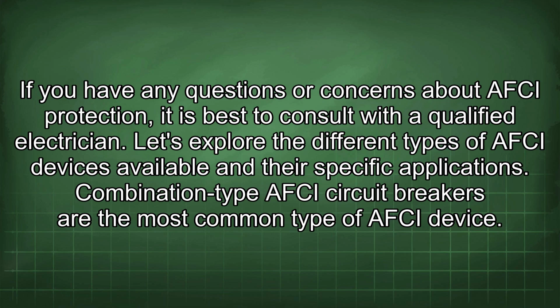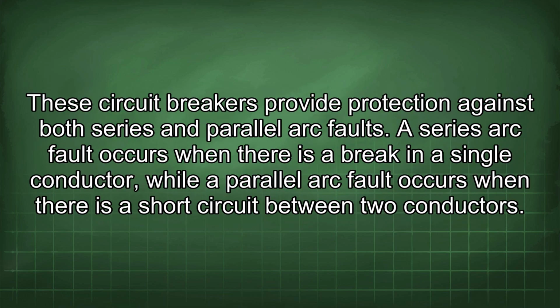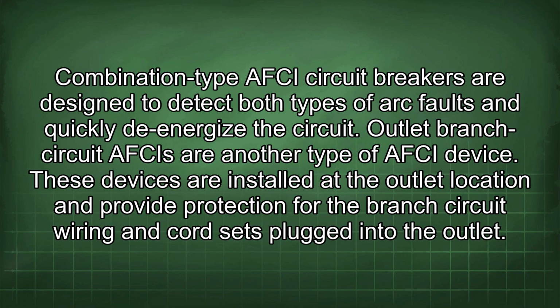Combination type AFCI circuit breakers are the most common type of AFCI device. These circuit breakers provide protection against both series and parallel arc faults. A series arc fault occurs when there is a break in a single conductor, while a parallel arc fault occurs when there is a short circuit between two conductors. Combination type AFCI circuit breakers are designed to detect both types of arc faults and quickly de-energize the circuit.